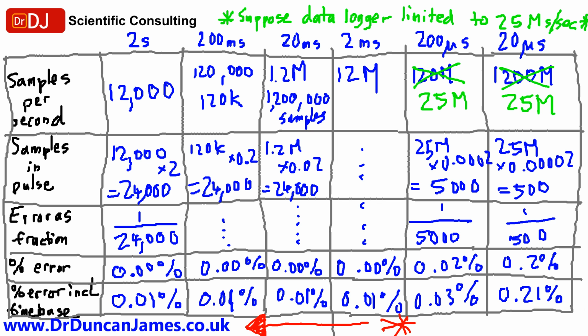And here again, I'm just leaving you with this overall grid. This is typically how I end up using it, so I can test a number of delays. And I'll often write all this out just so I'm really sure about what I'm doing on the day that I'm going to do some calibration.